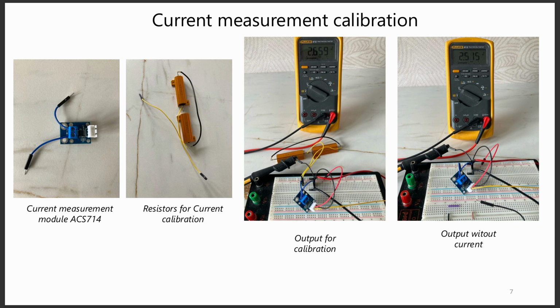But this device needs to be calibrated. So with a regulated power supply, 30 volts 5 amps, and 2 power resistors, you can produce a fixed current in the range of 1 ampere and see what's going on with the device.